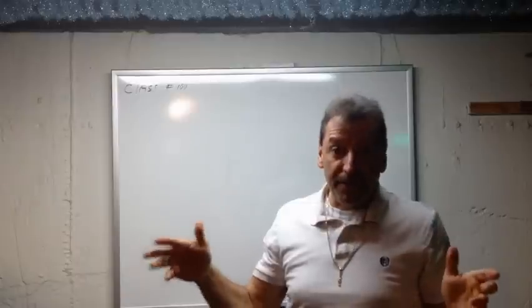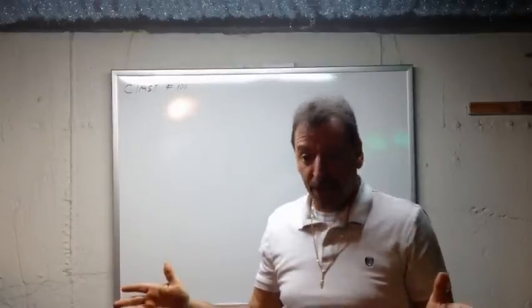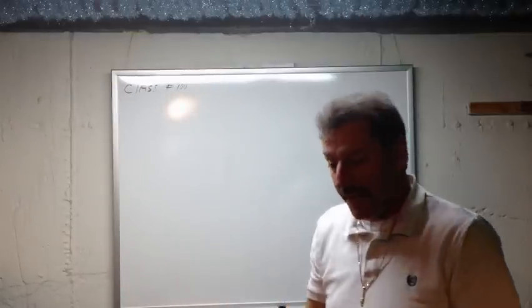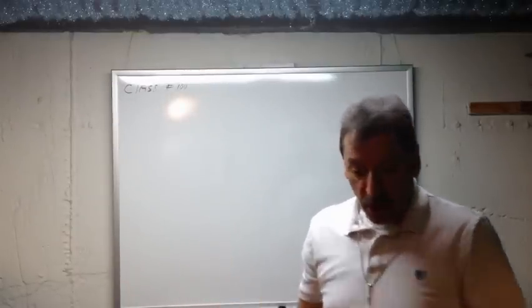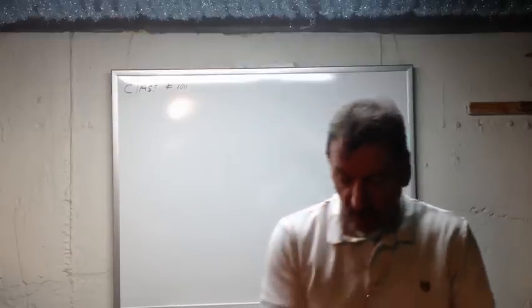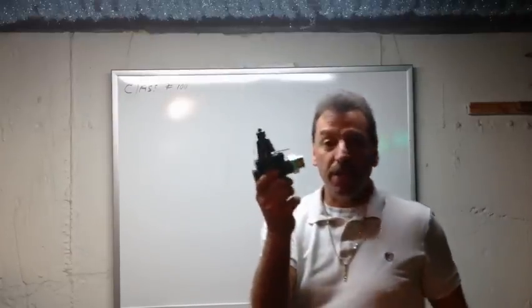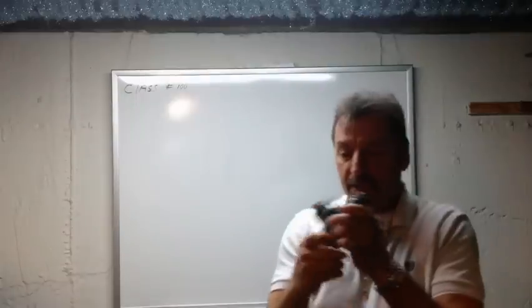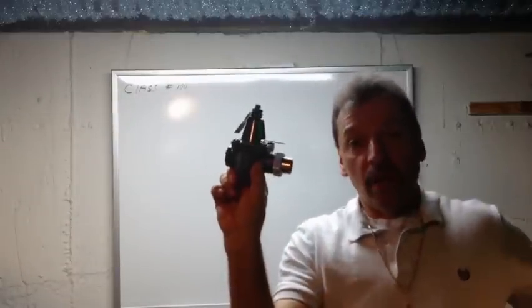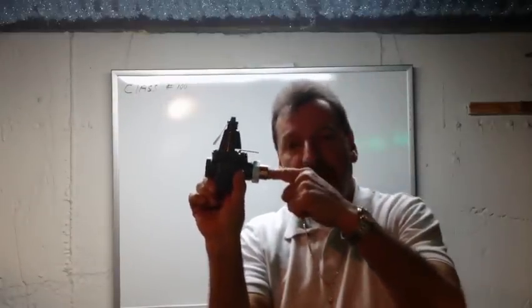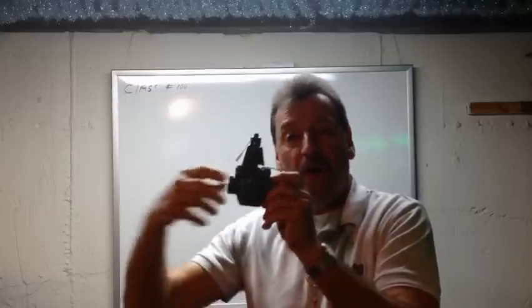Houses have 50 to 100 pounds of pressure, pounds per square inch, PSI, inside the home. So, of course, plumbers install this little gadget called the pressure-reducing valve, and it's a simple little invention that 50 pounds of pressure hits the back of the valve from the cold water feed into the boiler, but only lets 12 pounds of pressure out.